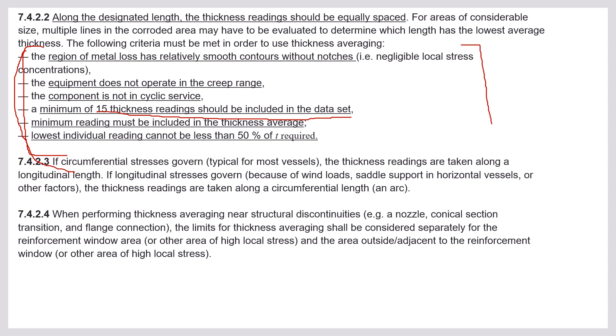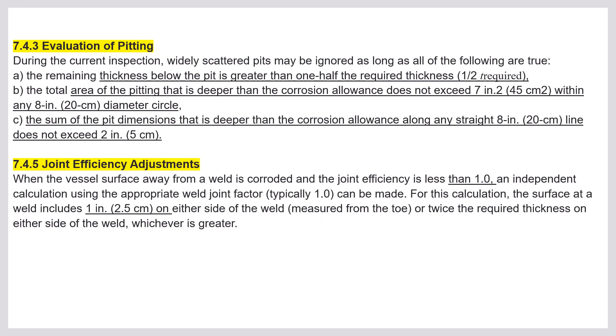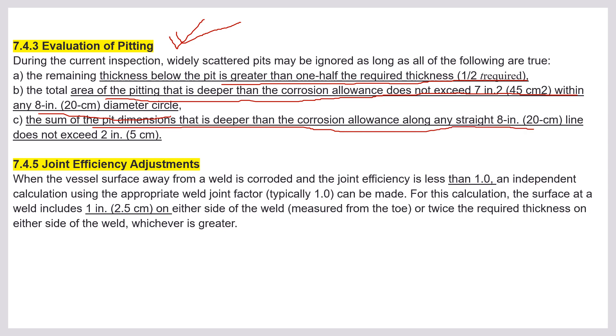Evaluation of pitting — this is a must question for the close-book exam. During the current inspection, widely scattered pits may be ignored as long as: the remaining thickness below the pits is greater than one half of the required thickness (0.5 × t_required); the total area of pitting deeper than the corrosion allowance does not exceed 7 in² (45 cm²) within any 8-inch diameter circle; or the sum of pit diameters deeper than the corrosion allowance along any straight line does not exceed 2 inches.